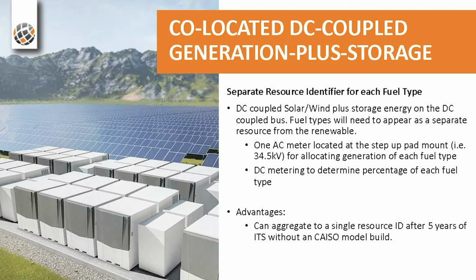And in this case, too, the DC coupling, what we're going to go through is DC coupling, how we're going to keep the two fuel types separate, the solar versus the storage. And how we do that is typically after the step-up pad mount transformer that goes from 600 volt typically to 34.5 kV, we have an AC meter. We have DC metering down below the inverter on each fuel type, which gives us a percentage of output.